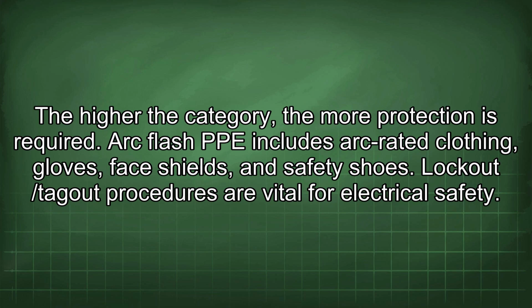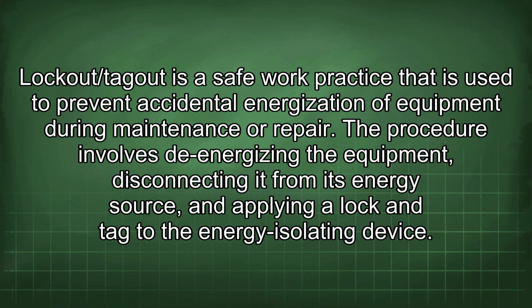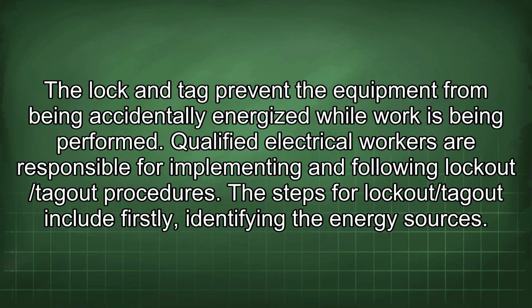Lockout/tagout procedures are vital for electrical safety. Lockout/tagout is a safe work practice that is used to prevent accidental energization of equipment during maintenance or repair. The procedure involves de-energizing the equipment, disconnecting it from its energy source, and applying a lock and tag to the energy isolating device. The lock and tag prevent the equipment from being accidentally energized while work is being performed. Qualified electrical workers are responsible for implementing and following lockout/tagout procedures.